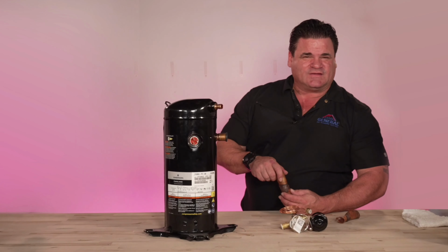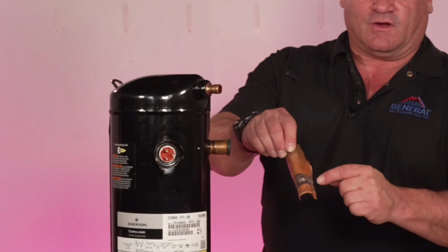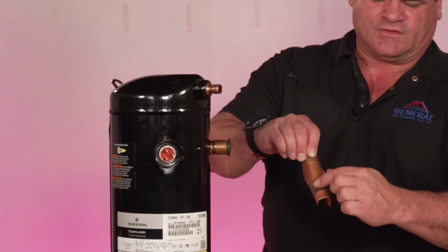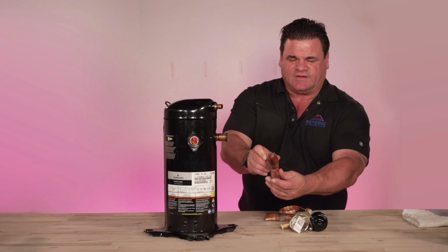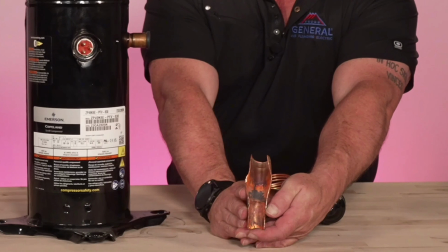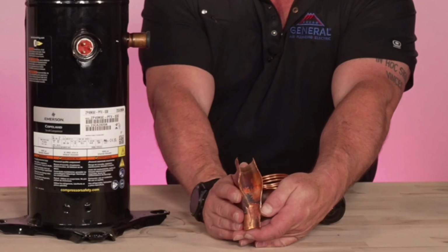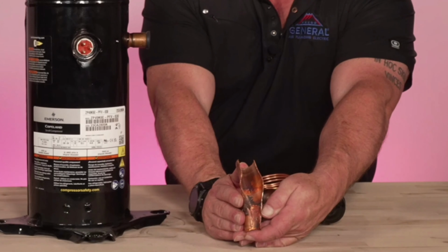Now, what does it do on the inside? Well, here's one, same thing. These are a little ugly because we had to cut them and get them opened up, but here's a braze joint on copper. I hope you can see this, but without the nitrogen flowing, there's oxygen present. And what you have is all of this oxidation on the inside of this copper.